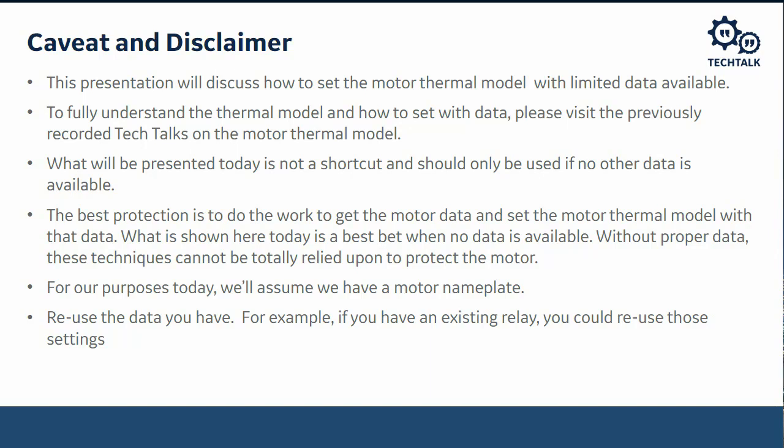So again, what I'm going to present today is not a shortcut. You should do your due diligence and try to set the motor thermal model based on the motor data. This is only meant to give you some guidelines or a best bet when there's no data available. Without proper data, these techniques cannot be totally relied upon to protect the motor. So you should think of this as a best bet to protect the motor when you don't have good data.